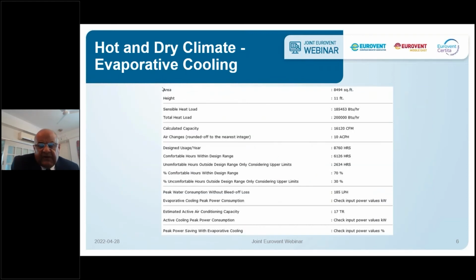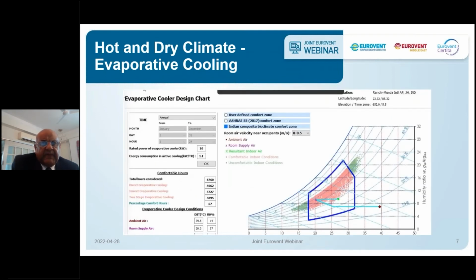This is a rough printout of that program, and it extends into two-stage evaporative cooling, where we first cool the air and then humidify it before releasing it into the space. For hot and dry regions, this could be a great thing to incorporate in airside air handling units in future, to reduce the load.